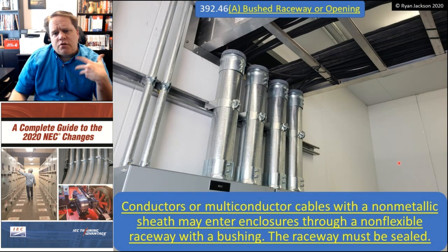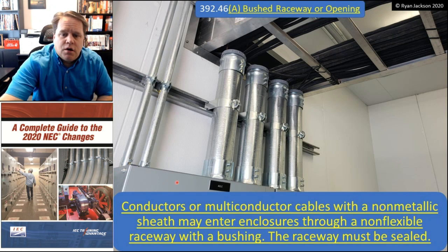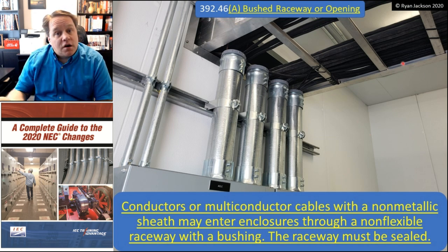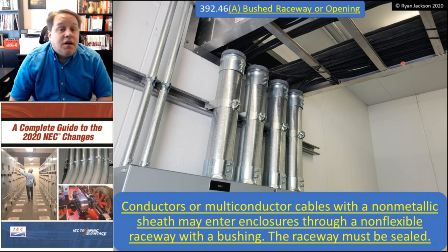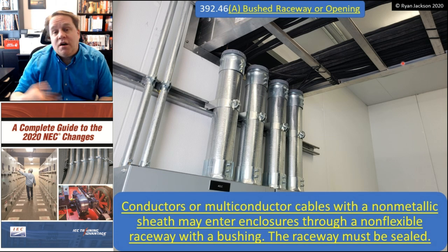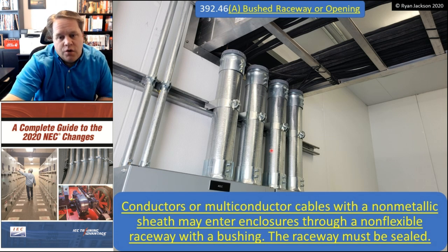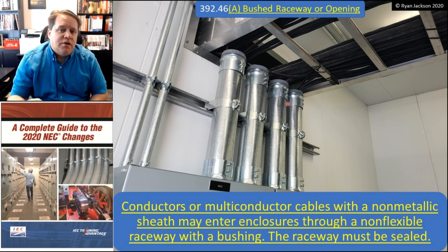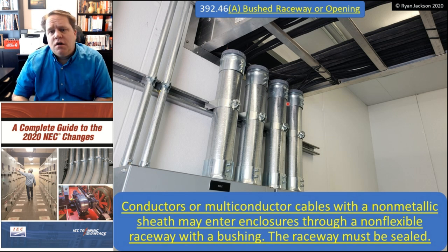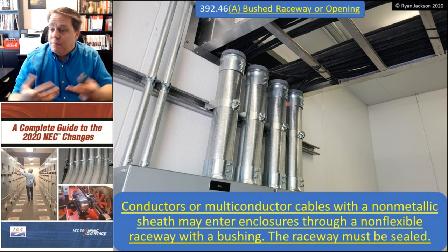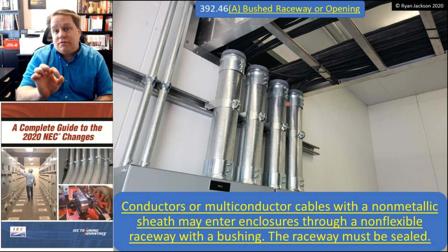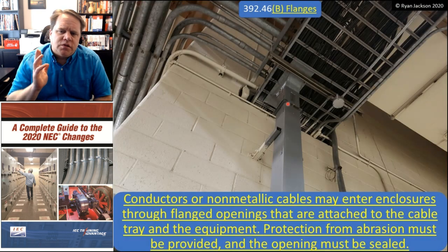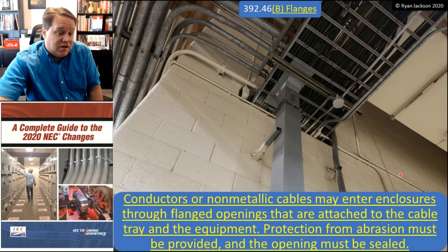We do not need a box where the conductors or cables enter the raceway, but we do need a bushing that protects them from abrasion. These bonding bushings have a plastic insert, which satisfies the rule. When entering an enclosure — going from the tray to the panelboard, for example — option A allows conductors or multi-conductor cables with a non-metallic sheath to enter enclosures through a non-flexible raceway with a bushing, and the raceway has to be sealed with something like duct seal putty to prevent flammable materials from getting inside the cabinet.